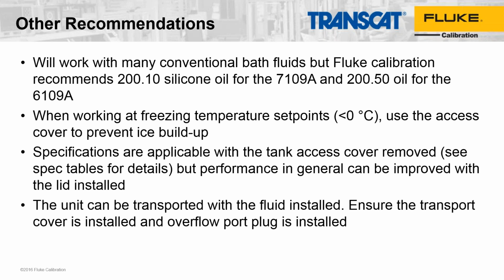then it possibly could change the specifications. And the engineers did test these baths with some different fluids just to make sure there was nothing strange that would happen. But silicone oil is the most common, certainly for this temperature range. But other fluids could be used, like some of them are hard to get a hold of nowadays, like the, what do they call it, fluorinert type fluids, alcohol, water, ethylene glycol, and they're not designed to work with salt, so we don't recommend putting salt in the 6109A.